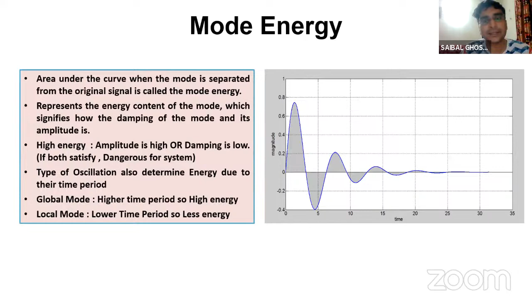That means in your system, there are thousands of machines or thousands of buses. So during the oscillation, which buses are oscillating against each other - that information you can generate using the phase angle of this oscillation. At every bus, the voltage or power is oscillating with some frequency. If you plot all of them, you will see that when in one particular bus voltage is increasing, at that same time in another bus voltage is decreasing - they are in the opposite direction.